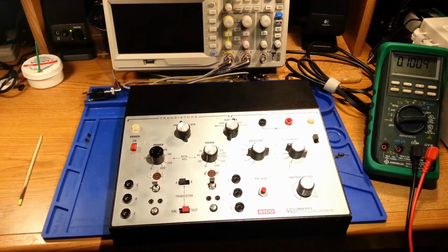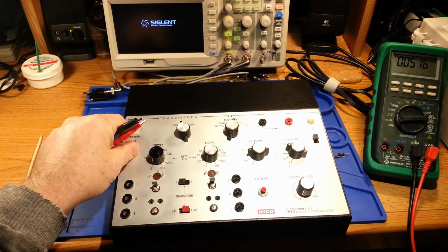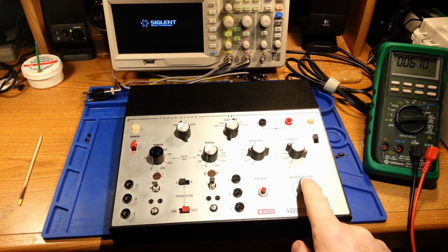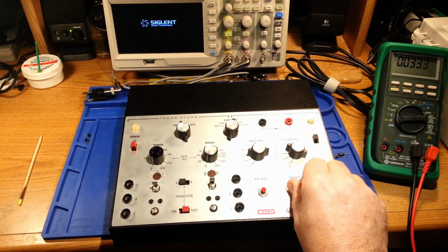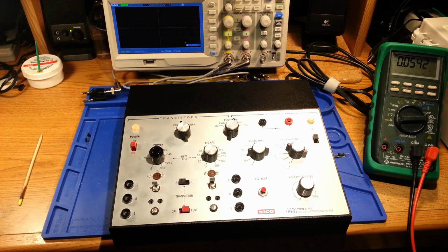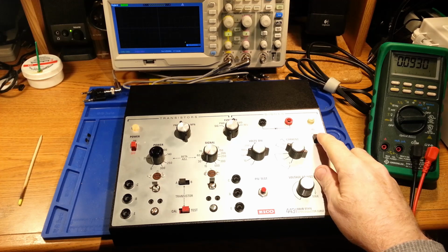It says power it on, rotate voltage adjust control fully counterclockwise. I can power it back up. Power's off here. I'm going to turn on my isolation transformer, which also turns on my scope, but that's fine. Power it on. Rotate the voltage adjust control, which is this one, fully counterclockwise. Connect AC line cord. Position power switch on, off switch to on. Position high voltage test cal switch to cal. So that's this one right here.